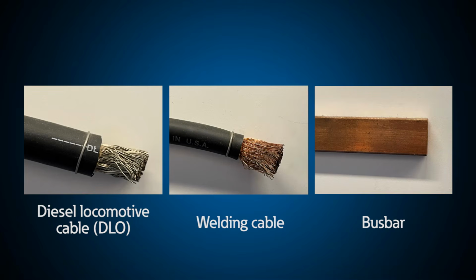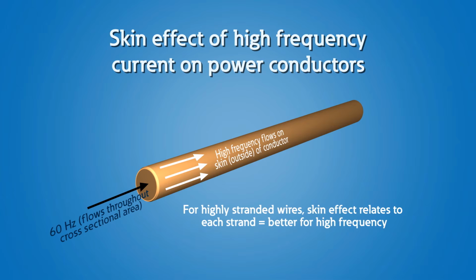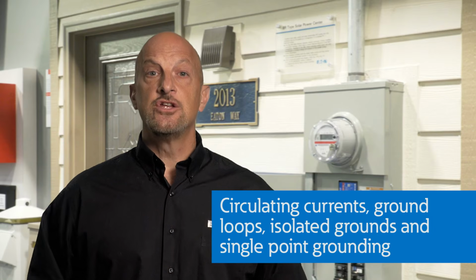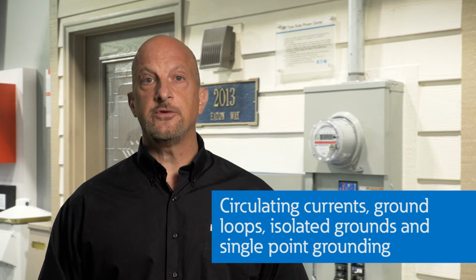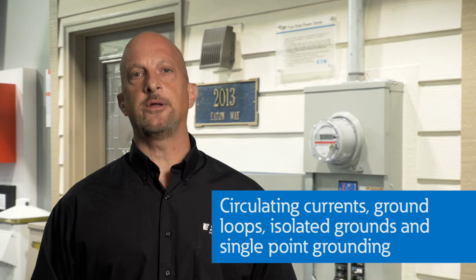In most cases, highly stranded and braided cable or bus bar with the shortest possible length is the most appropriate grounding method for high frequency currents, as it provides significant surface area for the skin effect phenomena of high frequency currents. Circulating currents, ground loops, isolated grounds, and single point grounding.